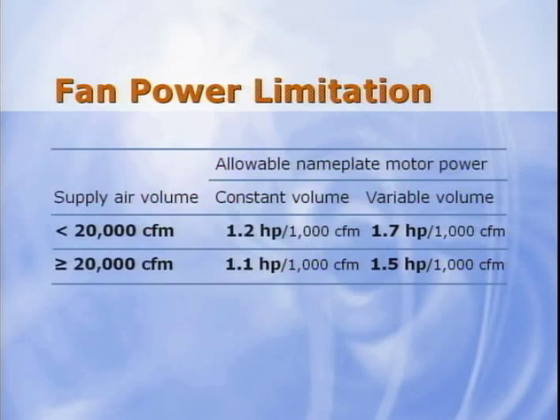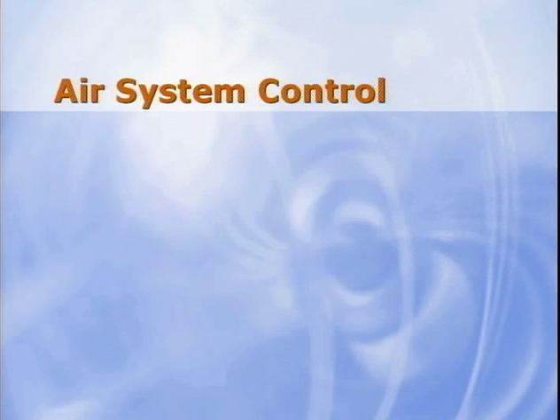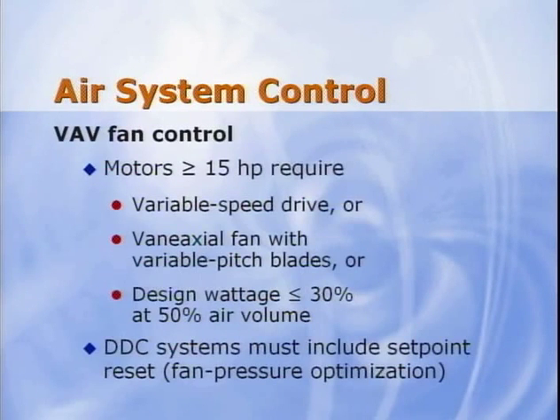Standard 90.1 nameplate horsepower limitations are based on system airflow and whether the system is constant or variable volume. There are credits for additional static pressure due to heat recovery, filtration above an inch, or systems delivering air colder than 55 degrees. Note, too, that the part load consumption of fan motors 15 horsepower and larger must comply with the requirements shown here if used in a VAV system. Many people meet this requirement by installing a variable speed drive on the fan. Finally, fan pressure optimization is required for systems with direct digital control. This will be covered in detail later.